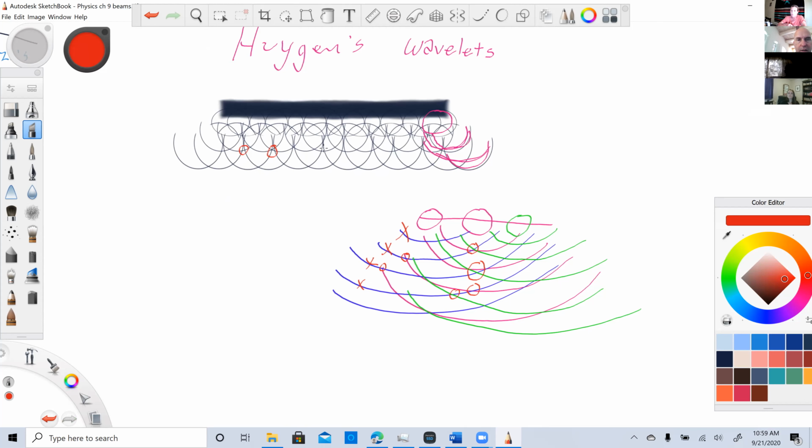So this is all where the waves cross, like this, is constructive interference. And what ends up happening is that you get constructive interference in the middle of the beam, in the middle of all these waves crossing over each other. Most, not all, but most of the constructive interference is right dead center in front of the transducer face.